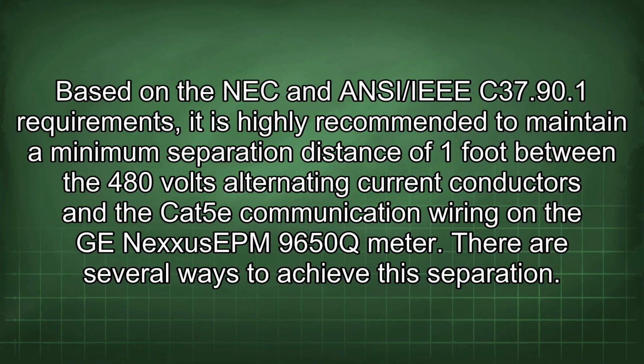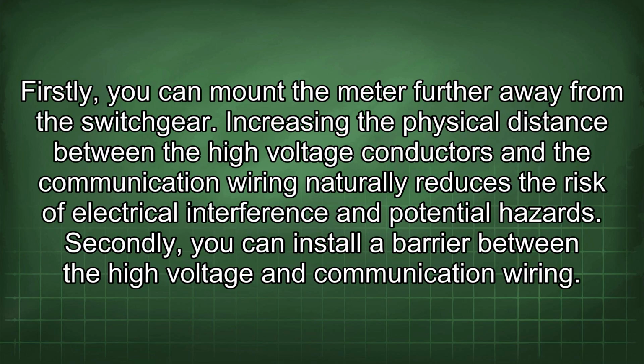There are several ways to achieve this separation. Firstly, you can mount the meter further away from the switchgear. Increasing the physical distance between the high voltage conductors and the communication wiring naturally reduces the risk of electrical interference and potential hazards. Secondly, you can install a barrier between the high voltage and communication wiring.